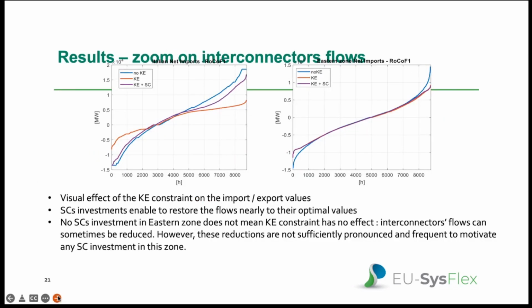So just to finish, we have here a visual effect of what I've just said about the impact of kinetic energy constraints. We're going to look at the first chart, which displays the duration curve for the import-export of Italy. The blue curve is for the reference case, and the red curve is when we activated the kinetic energy constraints. You can see that we cannot import as much as we did in the reference case, which explains why we have so much power shortage. On the left part of the graph, we cannot export as much as we did, which explains the risk of curtailment. The good news is that when we install synchronous condensers in Italy, we can restore the interconnection flows to similar values as in the reference case.